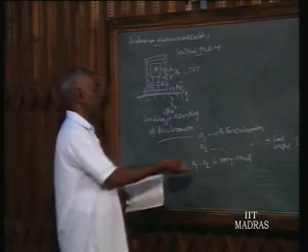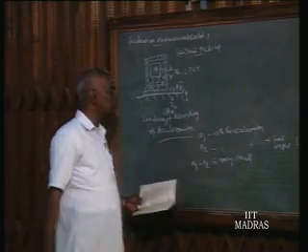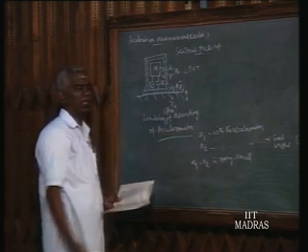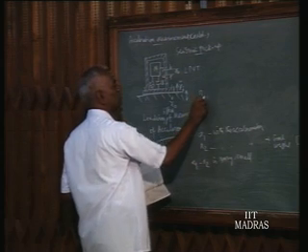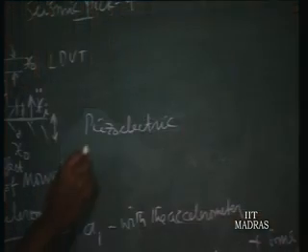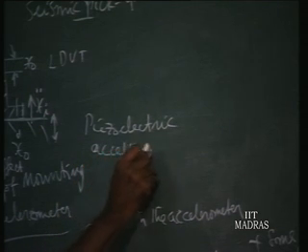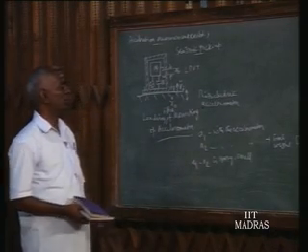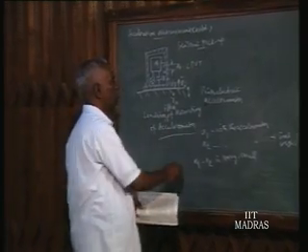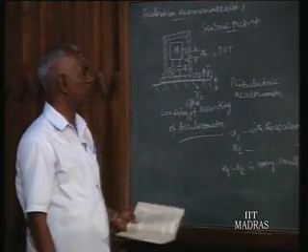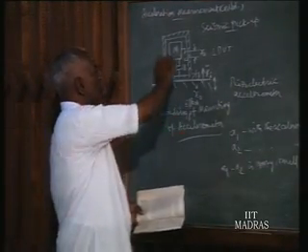If it is giving rise to a loading effect — if the difference is large — that means the accelerometer selected for this measurement is the wrong one. We should go for a lighter version. Mostly the choice is a piezoelectric accelerometer, which we have already seen. The problem with the piezoelectric accelerometer is that the acceleration should be a varying quantity — omega should be of the order of about 10 to 15 Hz depending upon the piezoelectric accelerometer. If it is a static measurement, we go for a lighter version of a different type.